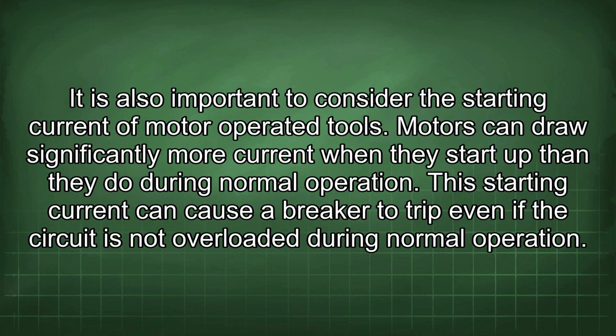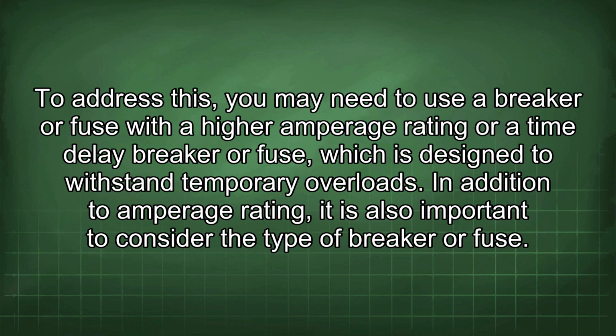It is also important to consider the starting current of motor-operated tools. Motors can draw significantly more current when they start up than they do during normal operation. This starting current can cause a breaker to trip even if the circuit is not overloaded during normal operation. To address this, you may need to use a breaker or fuse with a higher amperage rating or a time delay breaker or fuse, which is designed to withstand temporary overloads.